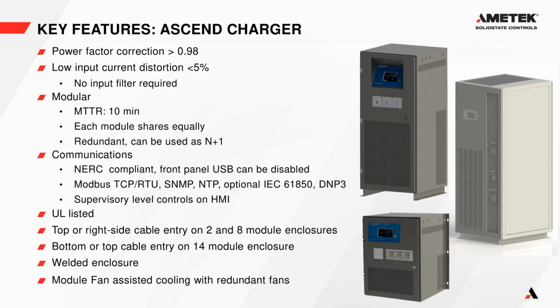When the system is running, each module shares the load equally. So if we have a 50 amp output and 5 modules, each module will supply 10 amps to the output. And if a module fails, the other 4 modules will take over immediately. So it can be used as an N+1 redundant system.